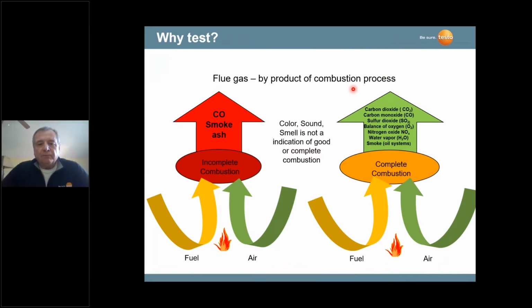Two things you need to know is there's a term called incomplete combustion off to the left, and a term called complete combustion. Complete combustion means that we have enough air to support the combustion process. Therefore, you can see here we have a balance of oxygen in the stack gases. So if you're using a combustion analyzer, hopefully it's a Testo combustion analyzer, you're able to measure oxygen at around 3, 4, 5%, maybe higher on residential gas furnaces or oil furnaces.